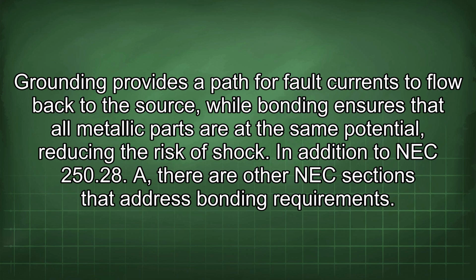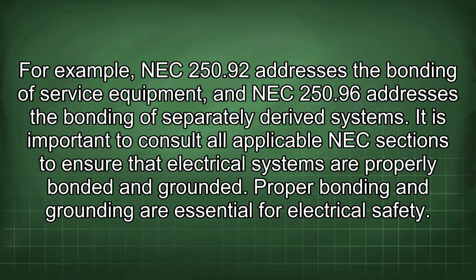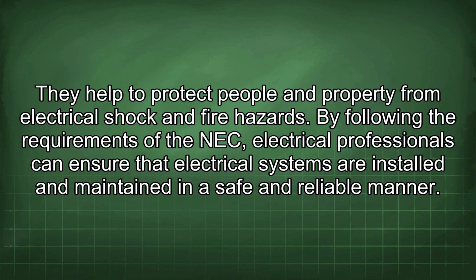In addition to NEC 250.28(A), there are other NEC sections that address bonding requirements. For example, NEC 250.92 addresses the bonding of service equipment, and NEC 250.96 addresses the bonding of separately derived systems. It is important to consult all applicable NEC sections to ensure that electrical systems are properly bonded and grounded. Proper bonding and grounding are essential for electrical safety. They help to protect people and property from electrical shock and fire hazards. By following the requirements of the NEC, electrical professionals can ensure that electrical systems are installed and maintained in a safe and reliable manner.